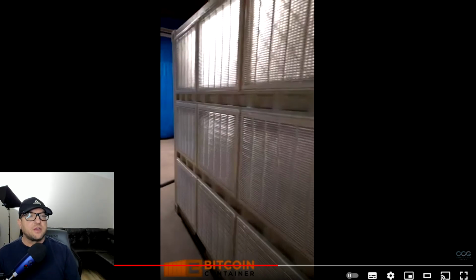So we built this, putting 9 slots and 9 filters in here, which worked out perfect for us. That way we had enough sucking power to pull all the hot air out, and we had the right kind of filters in there. If you only put 3 filters in with 15,000 CFM, you'd create such negative pressure it would suck out and destroy your filters. So keep that in mind — you have to know the rating of your filtration and the airflow it can accommodate.